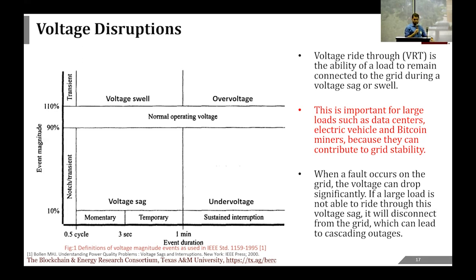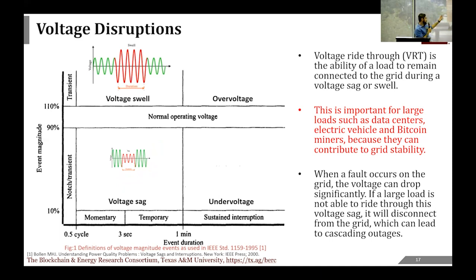When a fault occurs on the grid, the voltage can drop significantly, and if a large load is not able to ride through it, that could lead to catastrophic events on the grid. A voltage sag is when the voltage drops to a fraction of the nominal voltage, happening on timelines between 0.5 cycle (8.3 ms) and one minute. A voltage swell is similar but when the voltage goes higher than nominal. We also have overvoltage and undervoltage events, which are extended-duration variations.